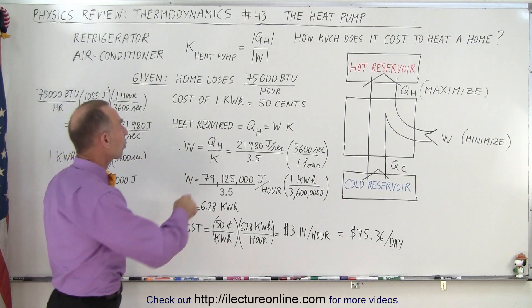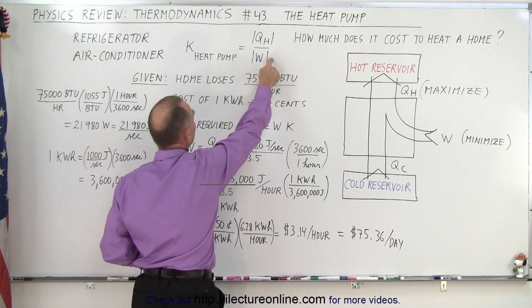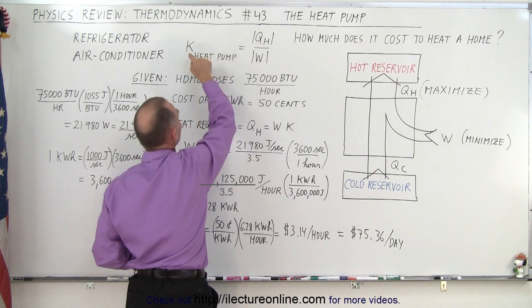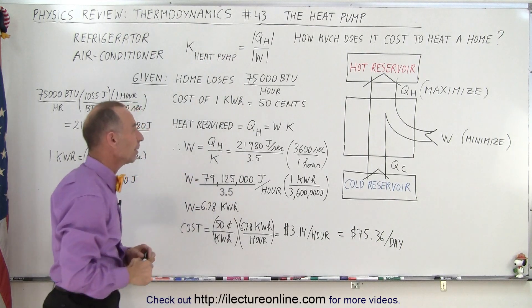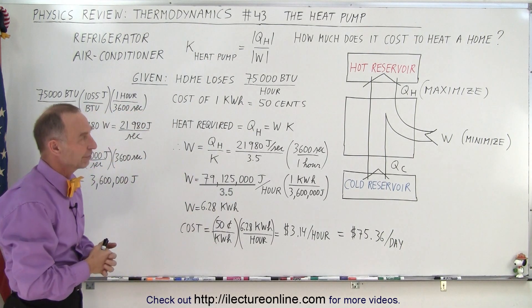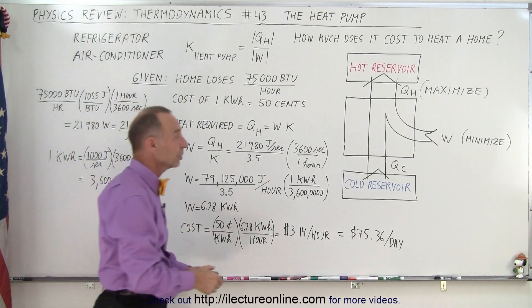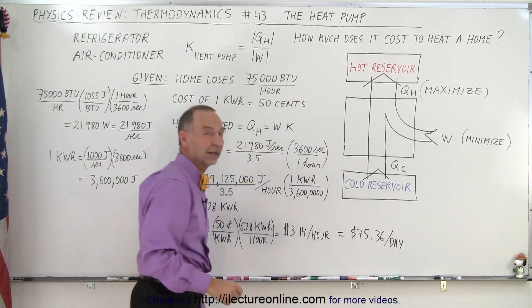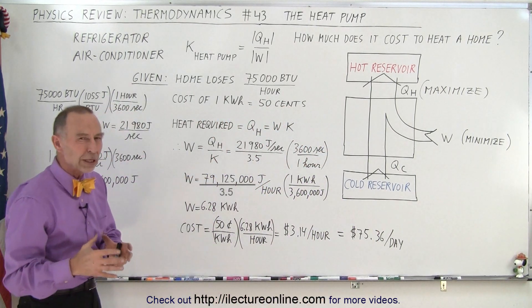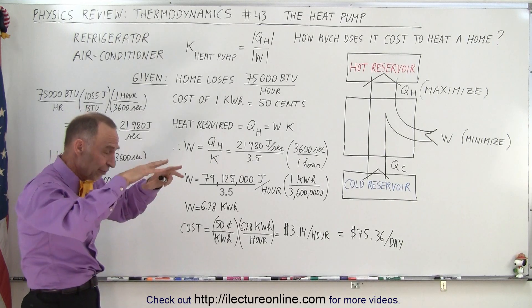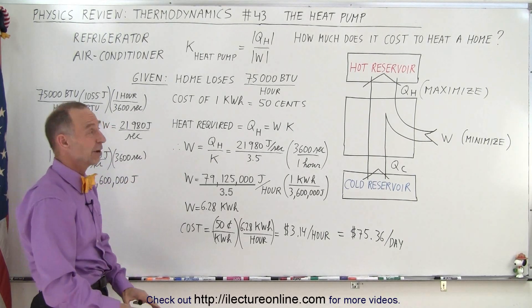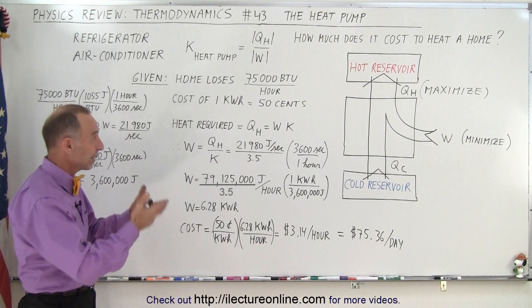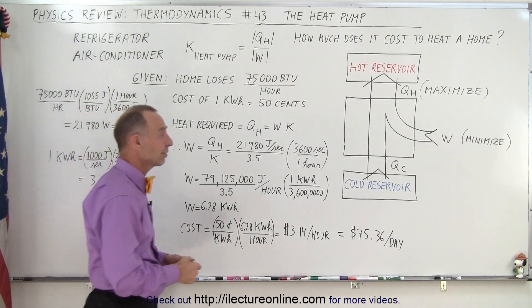So the heat required — we take this equation here — the heat required is going to be the work we put into it times the coefficient of performance of the pump. And let's say it's 3.5. Now that depends, of course, on how cold the air is outside. If the air outside is really cold, then your coefficient of performance drops. If the air outside is not as cold, then the coefficient of performance goes up. So it will depend upon how cold the air is outside.